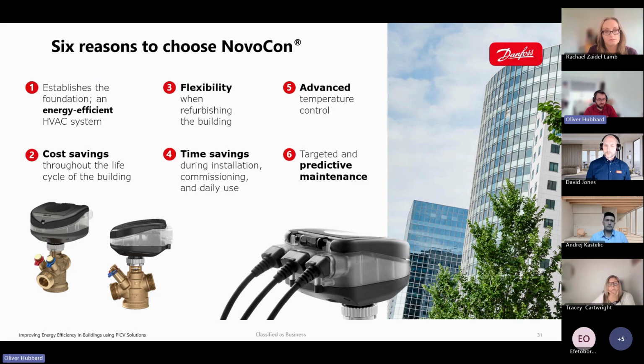A key thing to mention here is that instead of presetting the ABQM via the spindle, the NovoCon can actually be used to commission the valve, as it can adjust the stroke length based on the required flow and the valve that it's on. This is also key in saving time in the future on maintenance and when flushing the system. It can also be daisy chained together, so I think up to one power source can control 10 actuators. It also has advanced temperature control, which can be integrated within the BMS system.